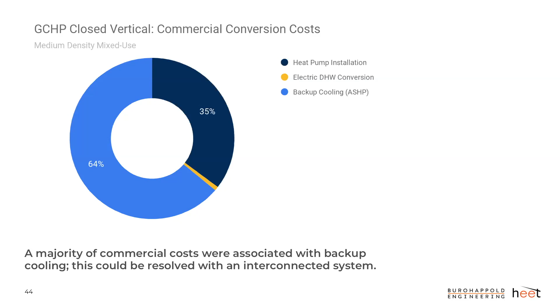On the commercial side, this is where the cooling really kicks in, or the lack thereof. Because you aren't able to meet 100% of your heating and cooling loads for commercial buildings with relatively higher cooling loads, you would need to retrofit with some sort of air source heat pump cooling system integrated with the ground source system. Even though you're paying more upfront to install a new cooling system, it nets out over time, because the savings from converting to an air source heat pump and avoiding typical air conditioning electricity costs makes it less expensive in the long run.